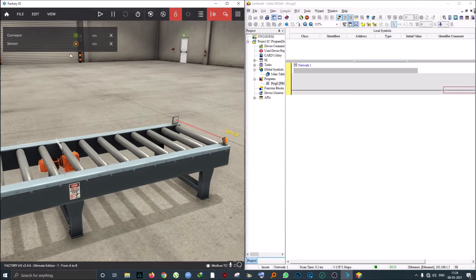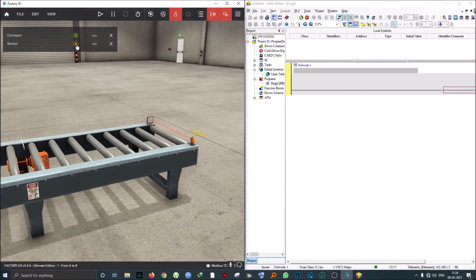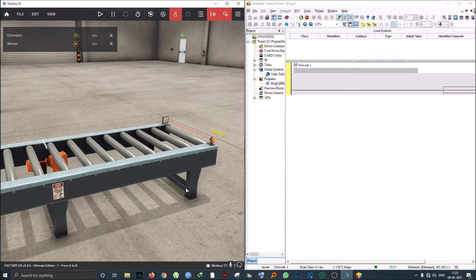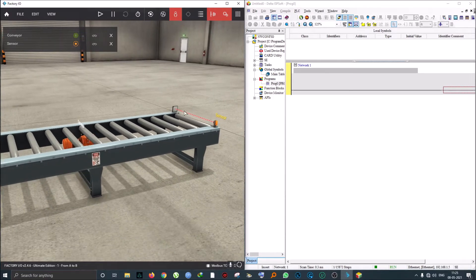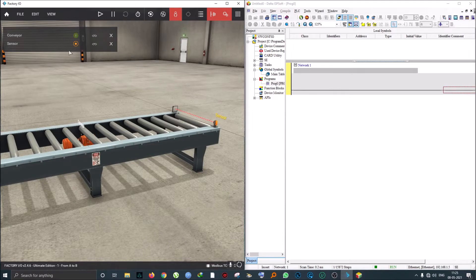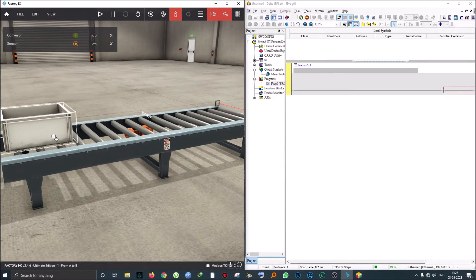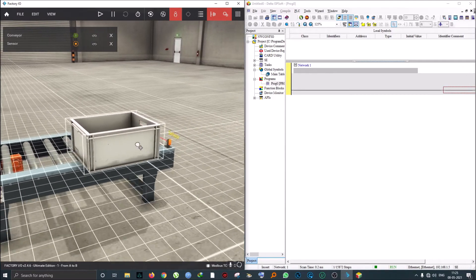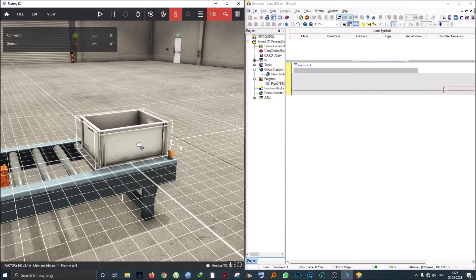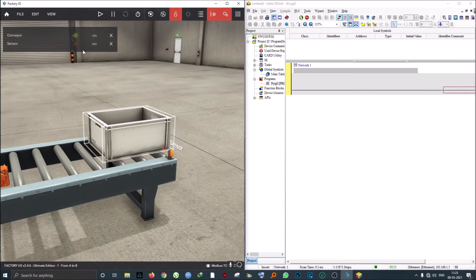You'll see the sensor is currently giving us an on signal. This is what we call a normally closed sensor. Without any object sensing, it's giving us a signal. If I actually take this object and pass it in front of the sensor, you'll see that it goes off. Remember that sensors in the real world are either electrically wired to be NO or NC sensors.